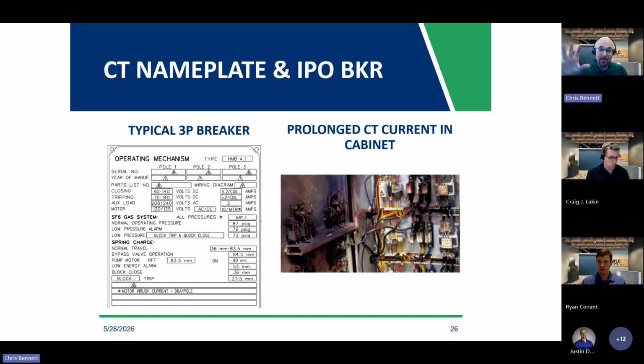But probably another big one that most folks on this call have seen before is the burning up of the CT circuits when there is a massive amount of fault current. Picture on the right there. Definitely not a fun event, and whatever we can do to keep folks safe is definitely number one priority.